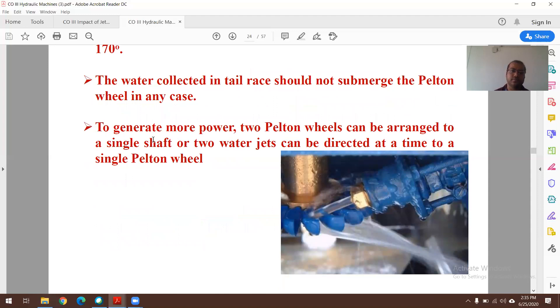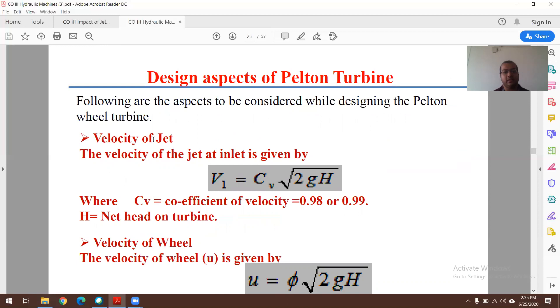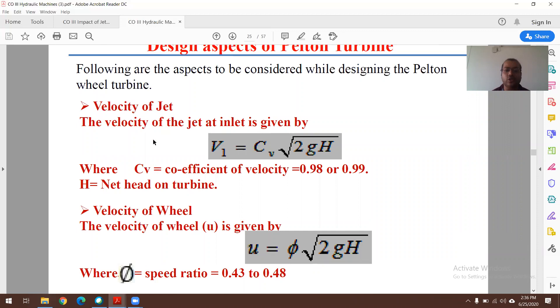For design aspects, the velocity of the jet is computed as V₁ = Cv × √(2gH), where H is the net head and Cv is the coefficient of velocity (actual velocity / theoretical velocity), with a value in the range of 0.98 to 0.99. The velocity of the wheel is found by u = φ × √(2gH), where φ is the speed ratio — a dimensionless term with a value in the range of 0.43 to 0.48.